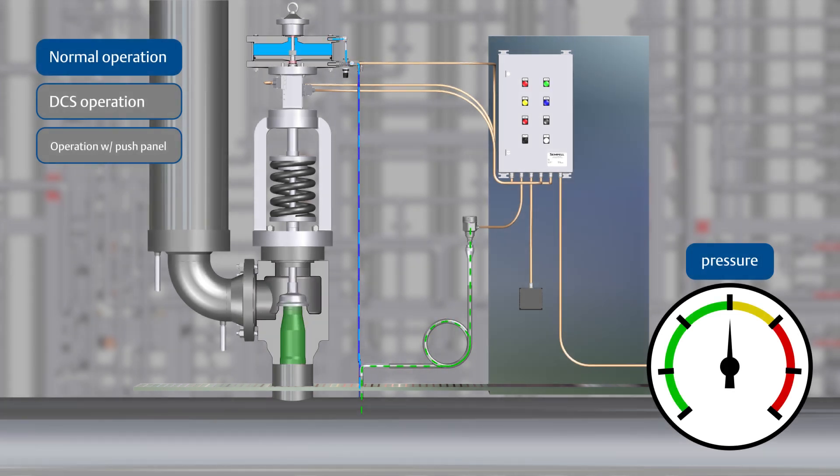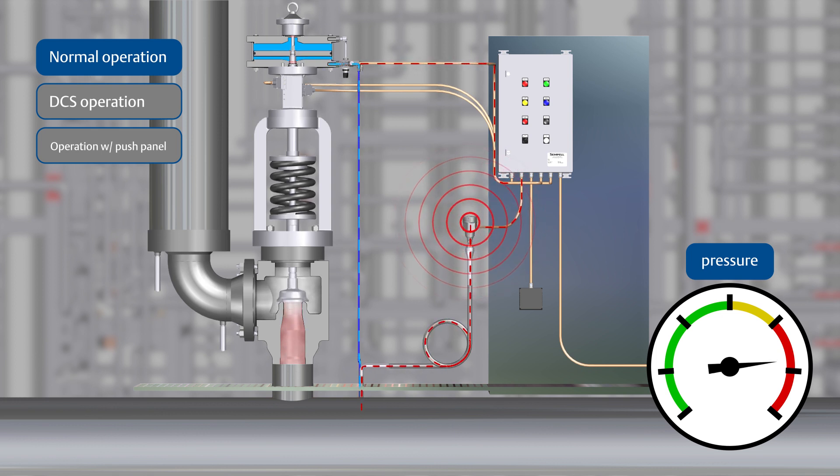The control unit acts independently in the event that the pressure switch detects a pressure higher than the set pressure, and switches the solenoid valve directly connected to the actuator of the valve. Loading air is relieved and lifting air is built up to safely open the valve.